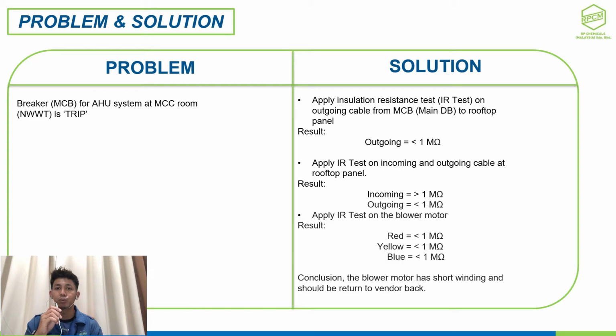For the last step to make a confirmation, I applied the IR test on each phase of the induction motor. So we got the result, which is that each phase of the induction motor is below 1 mega ohm. So the conclusion is the blower motor has a short winding and should be returned to the vendor.